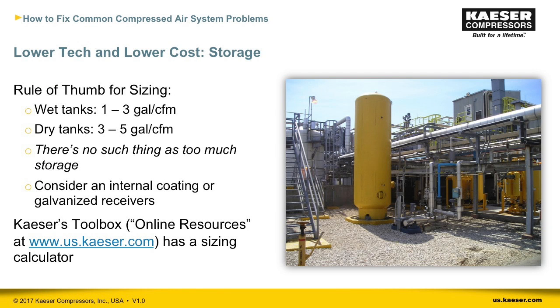If you want to know how large of a tank you need, here are some rough guidelines. Wet tanks should be between 1 and 3 gallons for every CFM in your system capacity. Dry tanks, 3 to 5 gallons. I would recommend you go larger with tanks because this is the one area where oversizing is never a problem. Also, it gives you room to accommodate future growth and expansion.